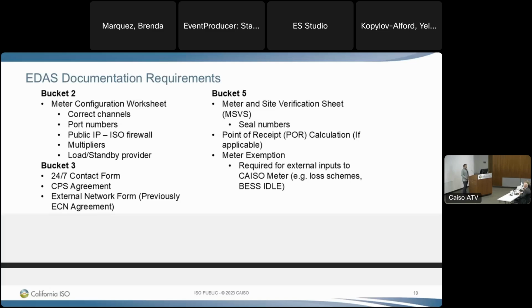For bucket 5, the MSVS: for seal numbers, a reminder that the seal needs to match who the inspector signatory is. There can be multiple inspectors at the site, so make sure whoever sealed the meter is also going to be the signatory, because the MSVS will get sent back if those two don't match. The POR calc is for situations where you might have a distance greater than half a mile to the POI, or low side metering schemes. This is determined by the CAISO inspector whether it's required, but it's processed in bucket 5. Work with your CAISO inspector on when this will be required, since they ultimately decide.